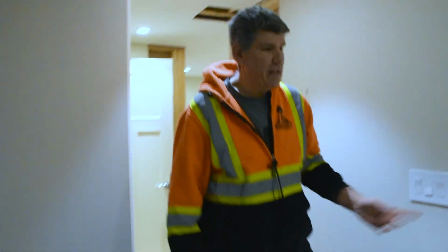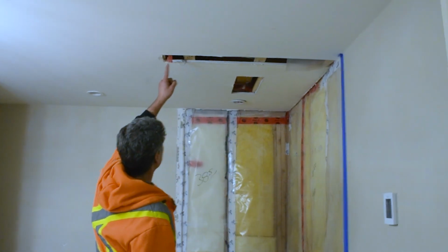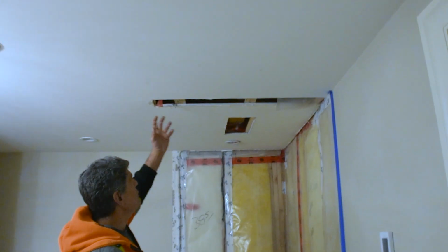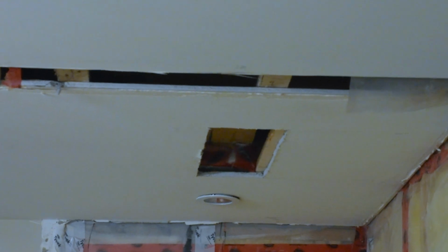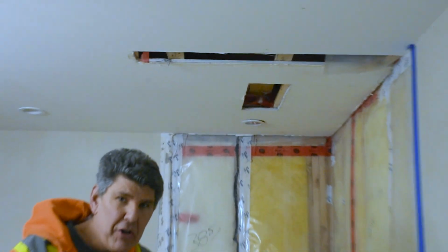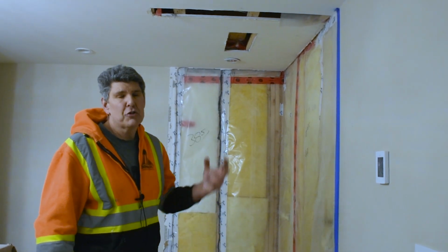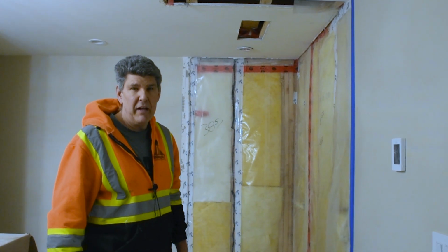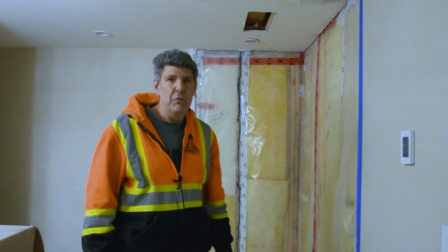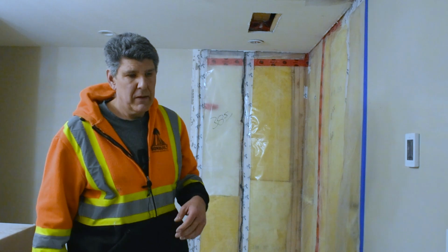Okay, come on along with me into this other room. So same thing, we're doing some changes here in the bathroom. When I put my hand up here, look at how this is blowing. We have major air leakage coming in, probably through the box joist. And so the air barrier wasn't properly done, and likely as well, there may not even have been a vapor barrier. So huge issues as we start to pursue this deep energy retrofit and how we're going to address this issue to bring this house down to what is a respectable air change rate.